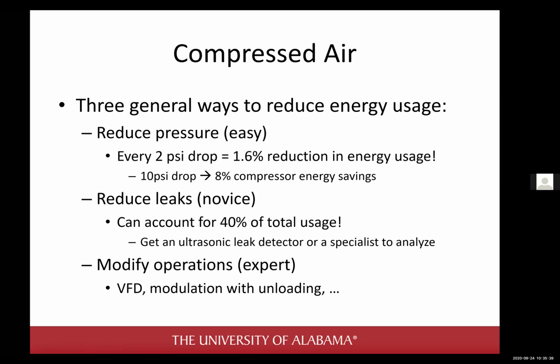3 general ways that I've written here. The first is reduce your pressure. You might be chugging along and making air at 100 PSI, and you might not need it. Most of the places I go just say, hey, it was like that when I got here. They're making air at 120 PSI, and I ask them, well, can you use 100 PSI air? And they say, I don't know. What I always recommend to plant managers, people who have control over that air compressor, is to dial it down 1 or 2 PSI, wait a week, see if anyone complains. Keep doing that until something happens. Hopefully nothing disastrous, and then turn it up a couple PSI just to be safe.